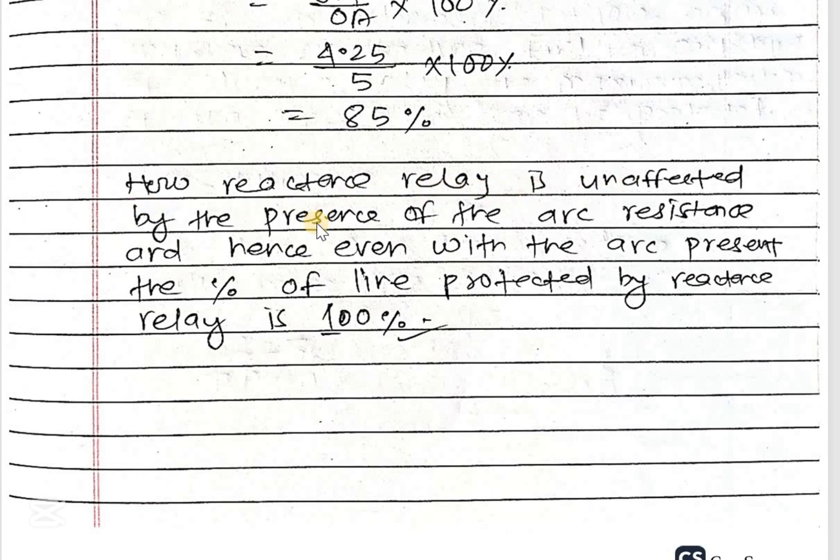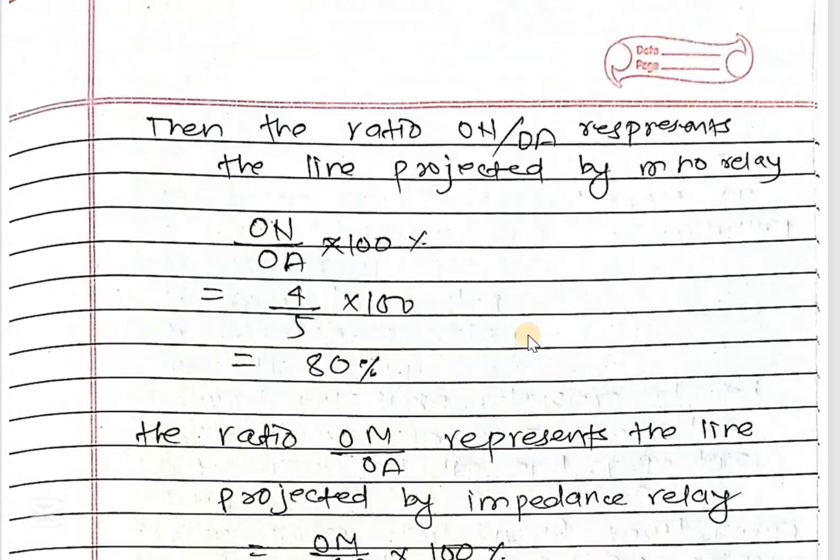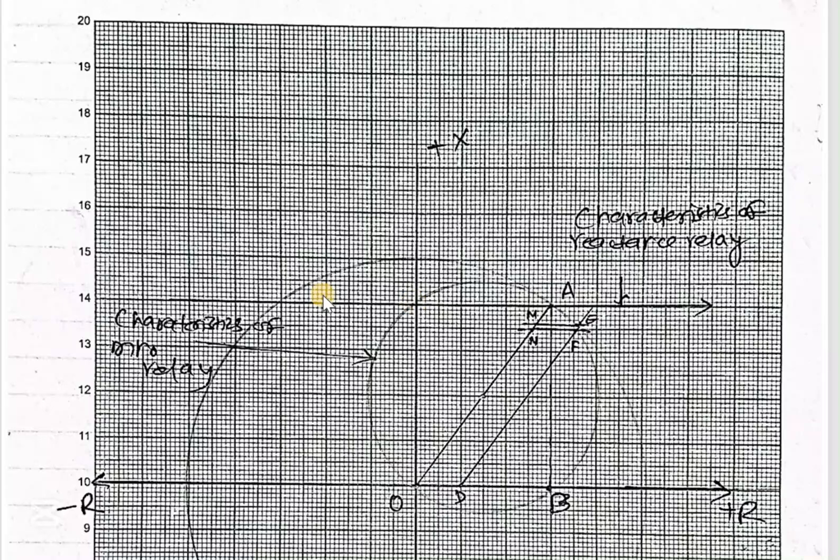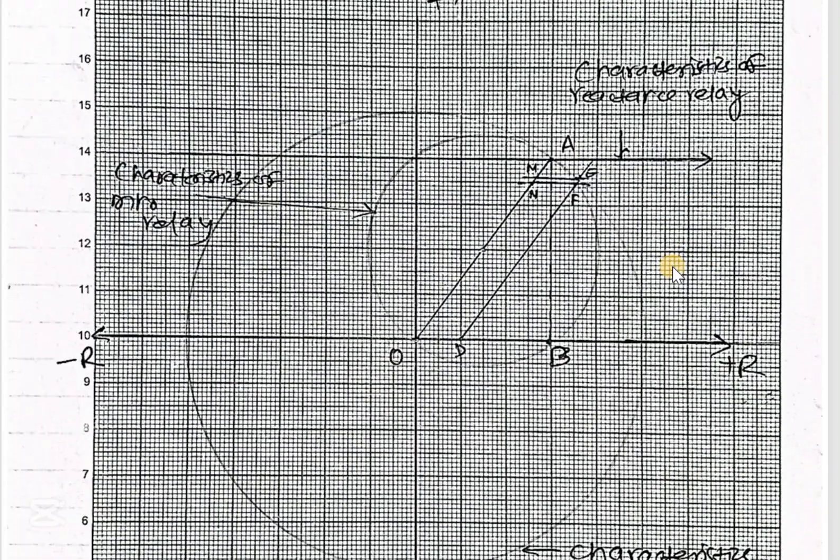Now the reactance relay is unaffected by the presence of arcing resistance, and hence even with the arc present, the percentage of the line protected by reactance relay is 100 percent. This one is the characteristic of reactance relay: 100 percent.